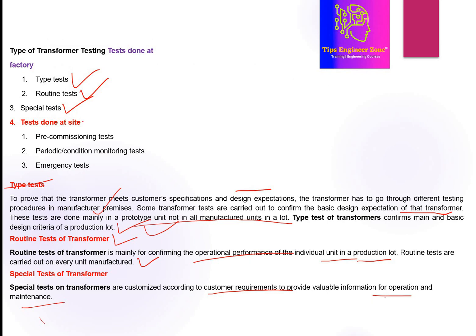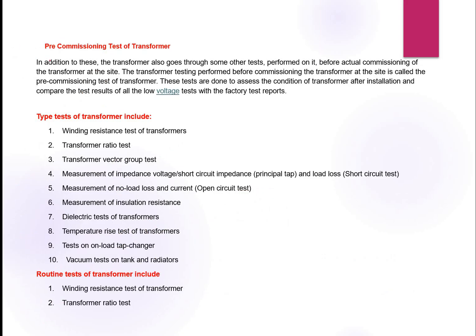The fourth is the test done at a site, meaning customer sites, not the production factory site. Tests done at a site mean pre-commissioning tests, periodic and condition monitoring tests, and emergency tests. The pre-commissioning tests are additional tests that the transformer goes through and that are performed on it before actual commissioning at the site. The transformer testing performed before commissioning the transformer at the site is called pre-commissioning.